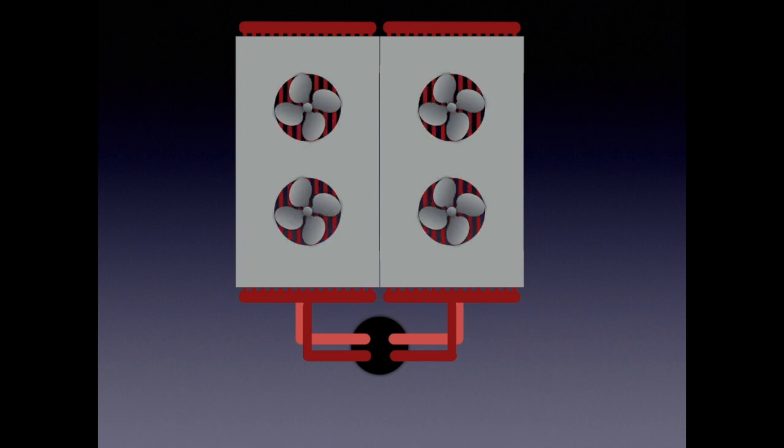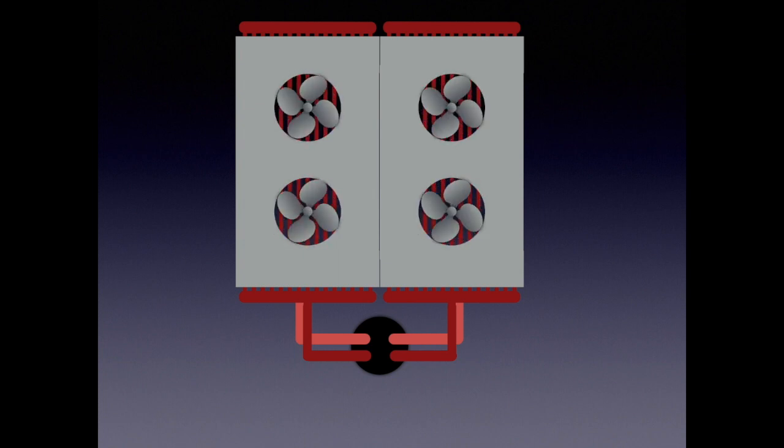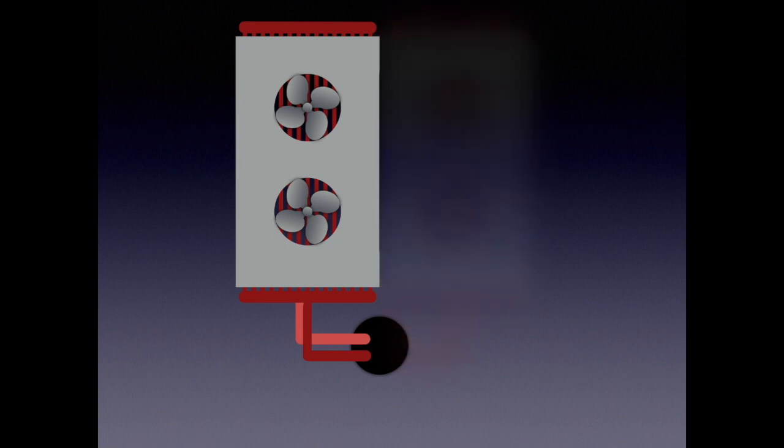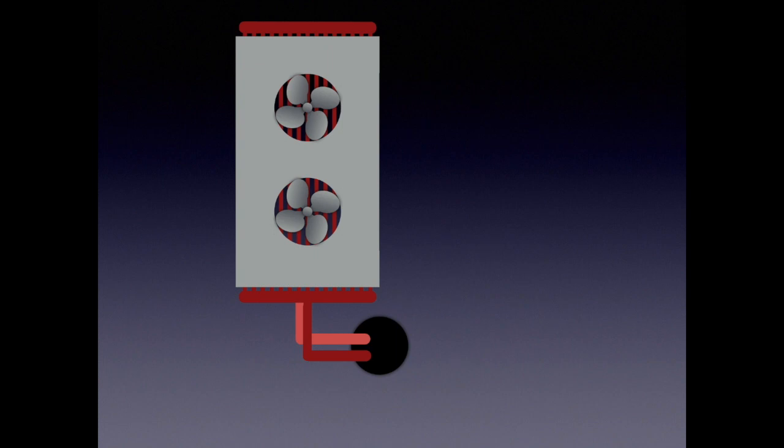100% hot vapor goes into the condenser and comes out 100% sub-cooled liquid into the condensate lines and back down to the rack room. Now when we go into split condenser and we do shut that valve, this is what we're doing. We're taking away half of that condenser.